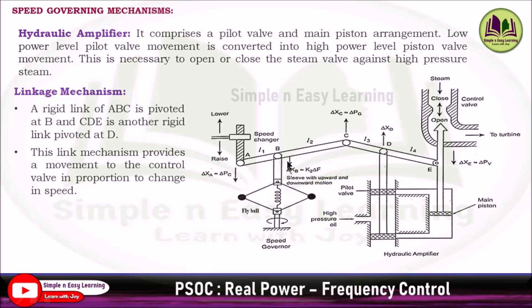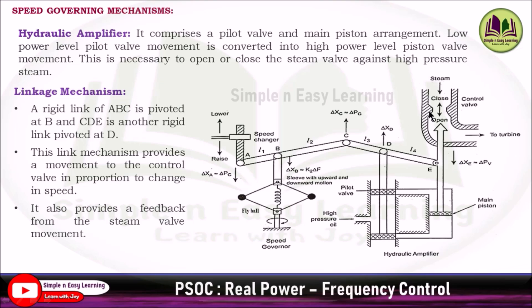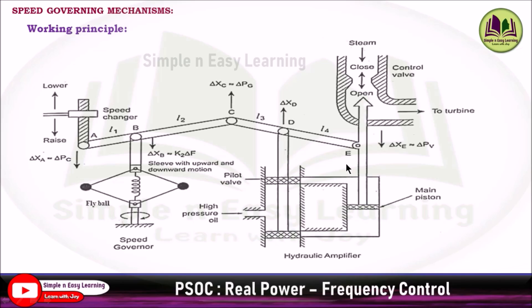The linkage mechanism consists of a rigid link A-B-C pivoted at point B, and link C-D-E pivoted at D. This linkage mechanism provides movement to the control valve in proportion to the change in speed. Whatever raise or lower command is given in the speed changer, the control valve opens and closes accordingly. It also provides feedback from the steam valve movement.